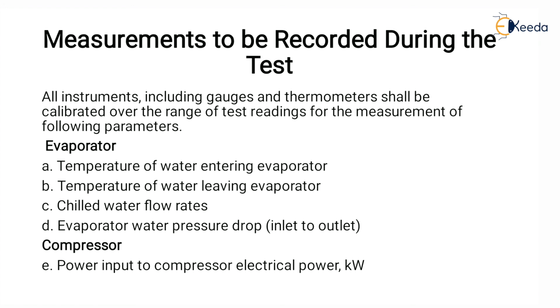Now the next is measurements to be recorded during the test. All the instruments, including the gauges and the thermometers, shall be calibrated over the range of the test reading for measurement of the following parameters. First is evaporator: the temperature of the water entering the evaporator, temperature of water leaving the evaporator, chilled water flow rate, evaporator water pressure drops. Next is compressor: power input to compressor, electrical power, that is kW.